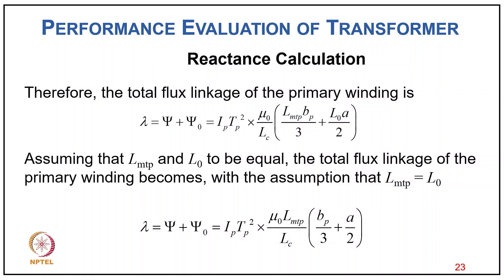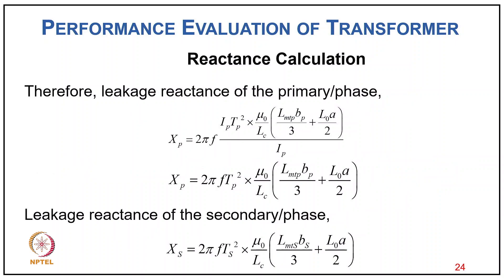With the assumption that LMTp = L0, the total flux linkage becomes λ = Ip×Tp² × μ₀×LMTp/Lc × [bp/3 + a/2]. Therefore the leakage reactance of the primary winding per phase is Xp = 2πf×Tp² × μ₀/Lc × [LMTp×bp/3 + L0×a/2], and similarly the leakage reactance of the secondary winding is Xs = 2πf×Ts² × μ₀/Lc × [LMTs×bs/3 + L0×a/2].